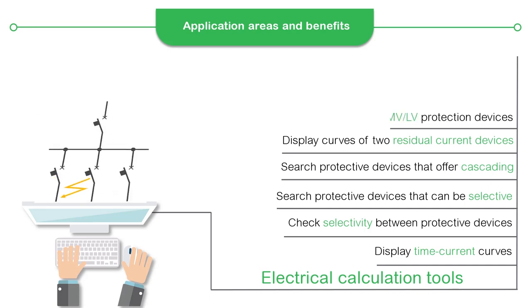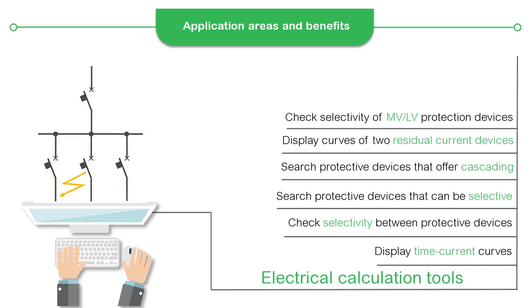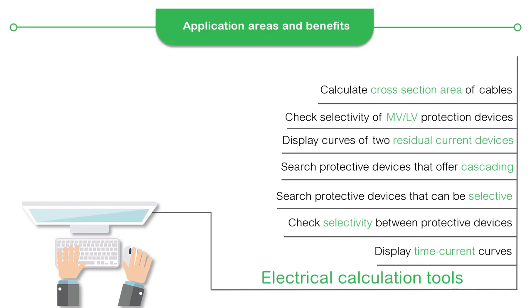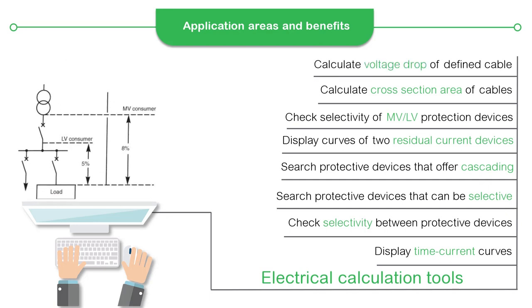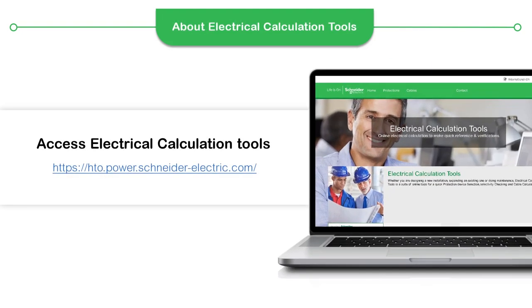Check selectivity of MV-LV protection devices, calculate the cross-section area of cables and build a cable schedule, calculate the voltage drop of a defined cable, and check the maximum length.